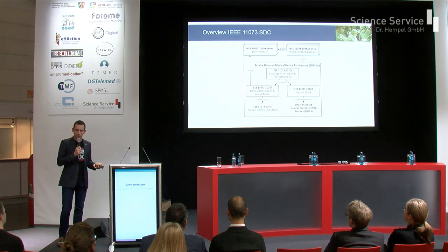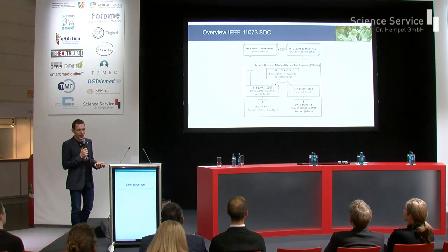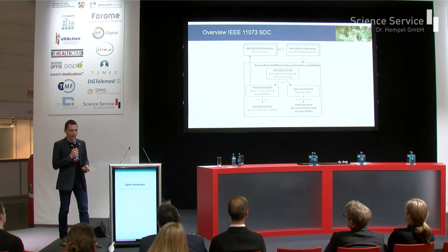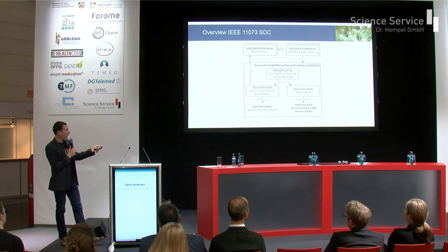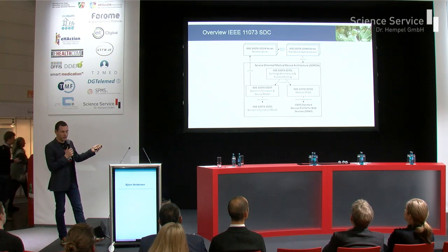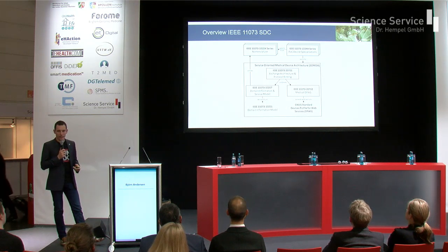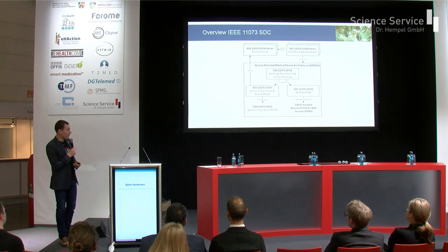Now, we have a structure definition, we have a transport technology. What's missing is semantics. We need to enable the machines to understand what the other one is saying. So we need codes, we need a controlled vocabulary, a nomenclature. And luckily in the 11073 series of standards that's already there, it's called the 1010X series. It's a couple of terminology standards from which you can draw controlled terms that have one well-defined meaning.